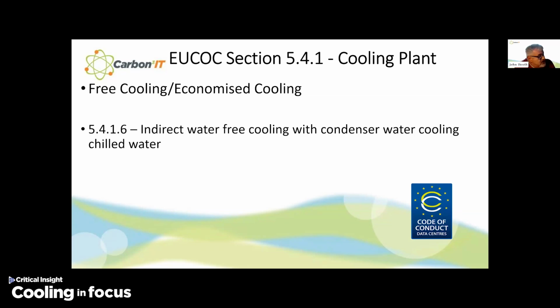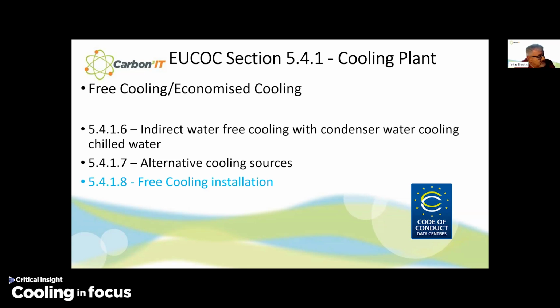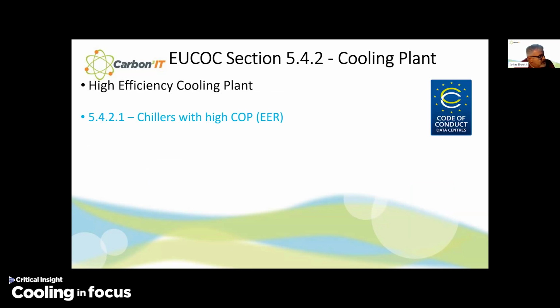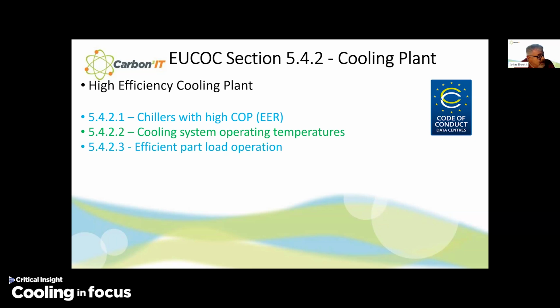And there's also some more best practices. So indirect water free cooling with condenser water cooled chilled water, potentially using alternative cooling sources. And you should consider free cooling installations for all retrofit within Europe. And I appreciate that that is easier to do in the north than it is in the south. High efficiency cooling plant. If you are going to use chillers, then choose one with high coefficient of performance. Think about your cooling system operating temperatures. Think about efficient part load operation.